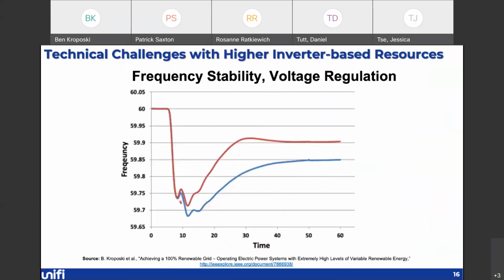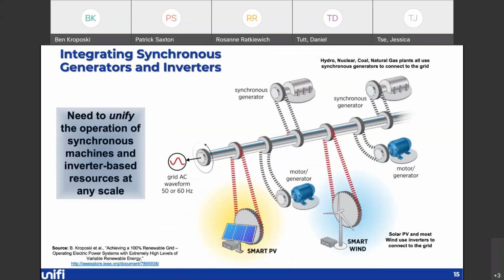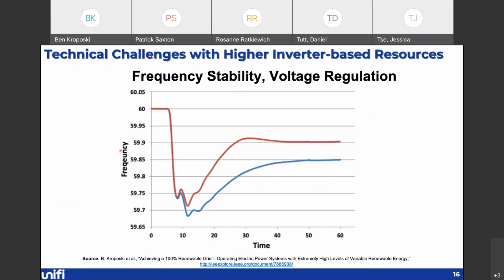I'll just list them quickly and talk about them. But one of the things that you need to maintain is voltage and frequency stability, right? So if we go back to this diagram here and we drop off one of these generators, that's what happens typically when you experience a big fault on the grid. So it's humming along at 60 hertz, you lose a generator and the frequency declines very rapidly until the rest of the generators can pick this system up. So this blue line represents how long it would take to recover that system, this is time in seconds. And then the red line here represents if we were to program the inverters that are online at a specific time, how it could improve that capability of bringing the system back to nominal frequency. This is typically what we call an inertial response. And for the inverters, we use the term fast frequency response for this characteristic, where we're able to detect this high change of frequency and have the inverter start to pull back the grid.